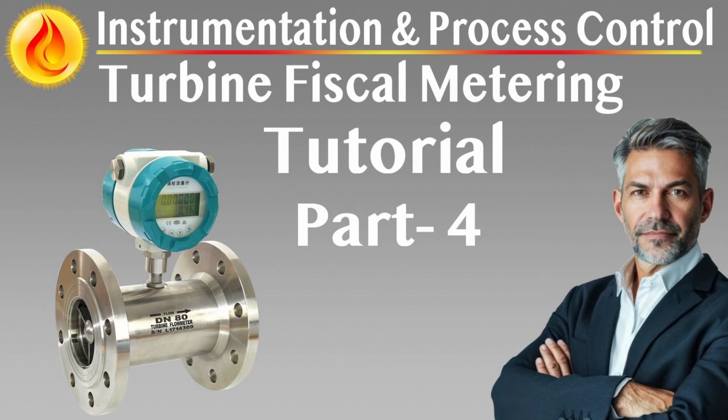Its core function is to poll the stream microcomputers and build a comprehensive database of measured and calculated values, including gross volumes, mass flow rates, standard volumes, densities, temperatures, and pressures. From this data, the station computer must compute station-wide totals and summaries, including the cumulative mass and volume flow across all active meter runs. The station microcomputer must support both periodic and on-demand report generation.